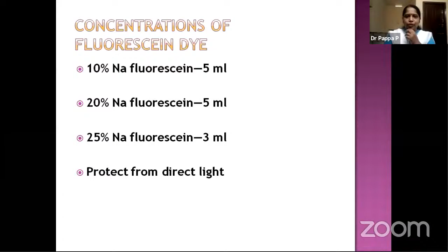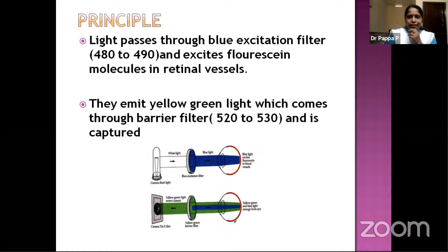And this is the principle. When the light passes through the blue excitation filter in the camera, it will reach the patient's retina and excite the fluorescent molecules on the retinal vessels. They emit a light of different wavelength, that is a green light, and this green light passes through the camera's barrier filter and is captured by the camera.